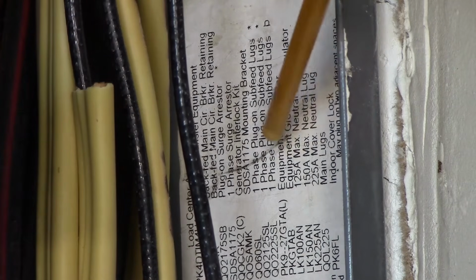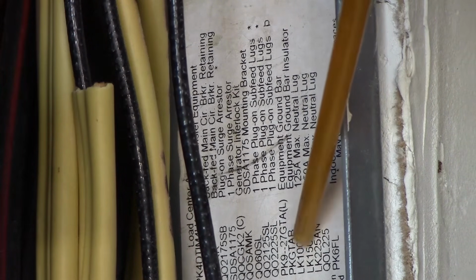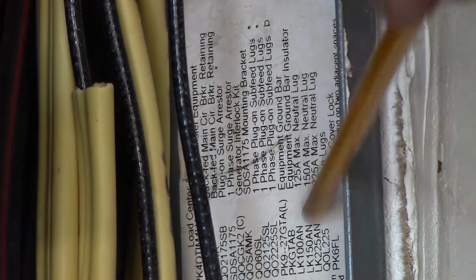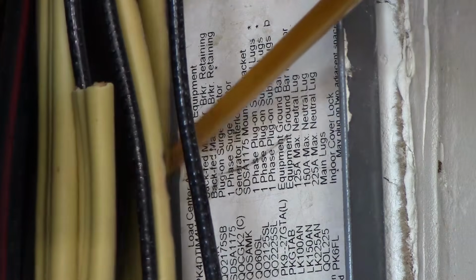And the last thing that I wanted to show on here is when we look up here, this is where you actually will find all the additional components that can be used in this cabinet. For example, when we talked about that equipment grounding bar, we have it available here. That can go in here. The screws are right back here. That's the model that you would look up in order to find the proper bar that goes in this panel if you're going to do a remote distribution panel where you have to separate the grounded conductors, which are the neutrals, and the equipment grounds. Okay, that's where you want to find the size. So this is where you get it. Right here, and it fits right in some screws that are located back here, back behind these wires.